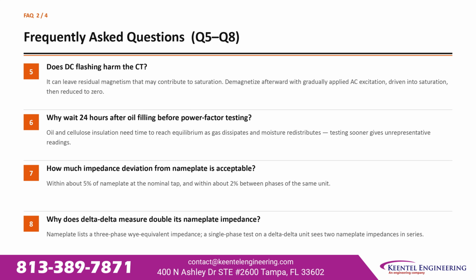How much impedance deviation from nameplate is acceptable? Within about 5% of nameplate at the nominal tap and within about 2% between phases of the same unit. Why does delta-delta measure double its nameplate impedance? Nameplate lists a 3-phase Y-equivalent impedance. A single-phase test on a delta-delta unit sees 2 nameplate impedances in series.